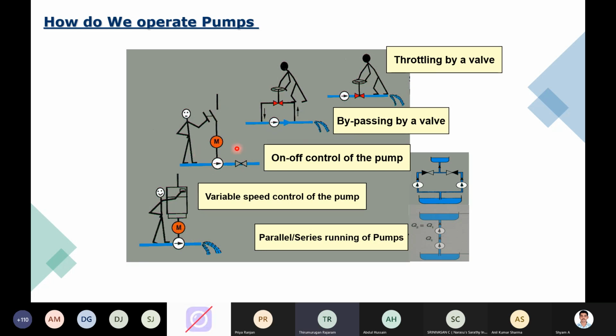The on and off control method is just to start and stop the pump whenever the requirement arises. This will have a high starting current, but compared to throttling or bypass, it is a little bit more energy efficient. The foremost energy efficient system is operated on variable speed control of the pump. It is nothing but a VFD, which helps you control the speed of the motor. In turn, the motor reduces the pump speed, and the pump delivers the lower flow or rate for the situation. This method, variable speed control of pumps, is being adopted in many industries.